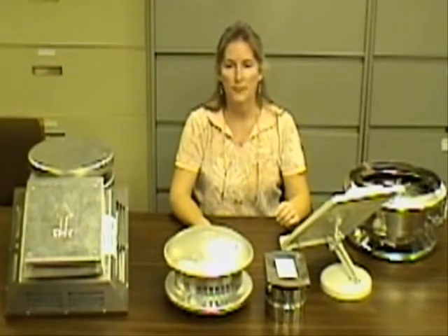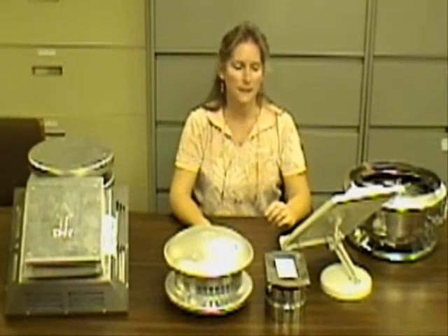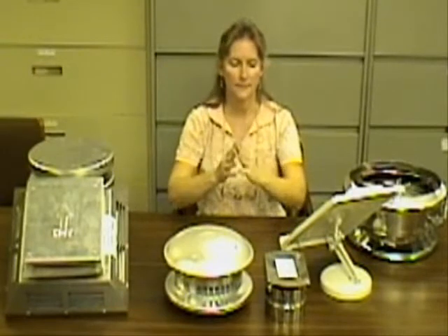What might not be as clear is why some systems are permitted to terminate horizontally when others require that it must be a vertical termination. Most of the venting products in the residential line are used with natural draft appliances. Since these appliances rely on the fact that hot air rises to properly and safely vent, they must terminate in the vertical position. Hot air rises, so the vent pipe points upward to help the flue gases leave.